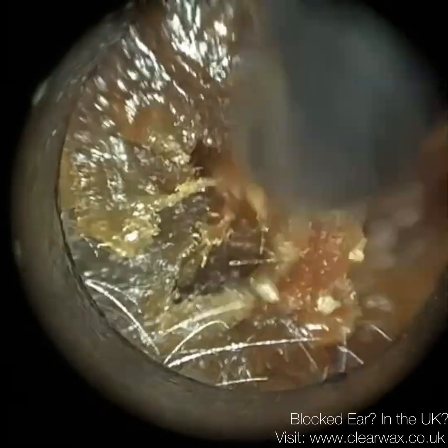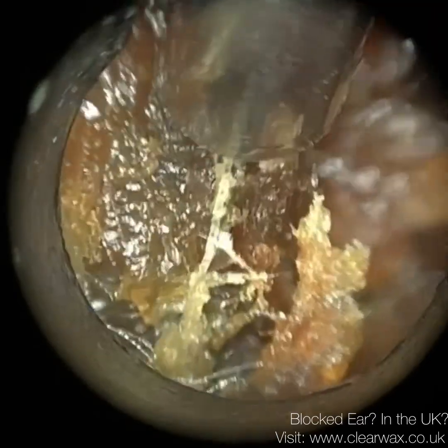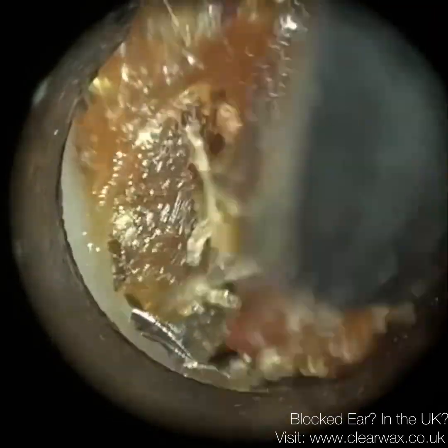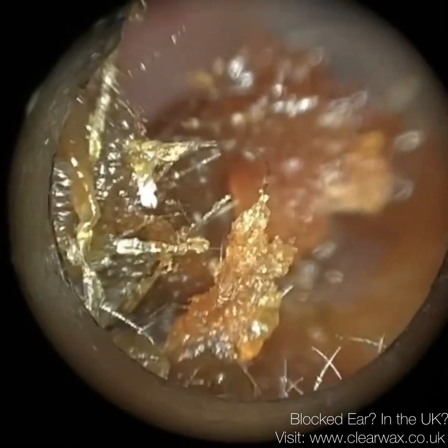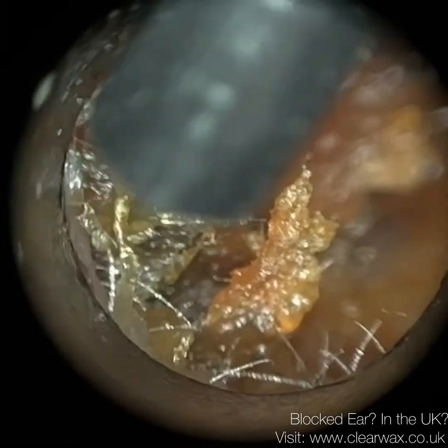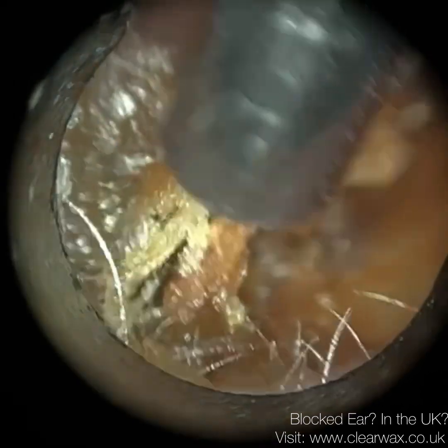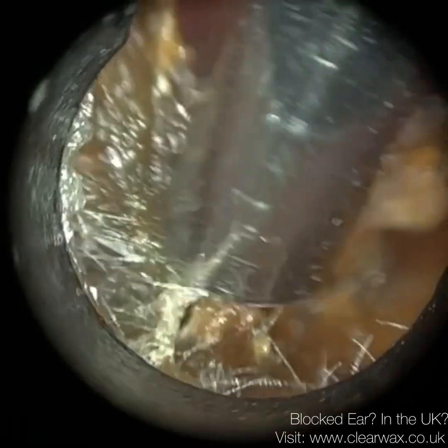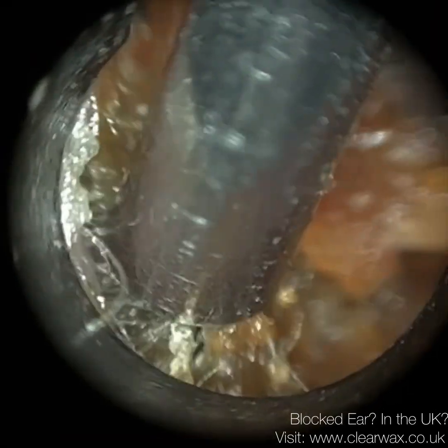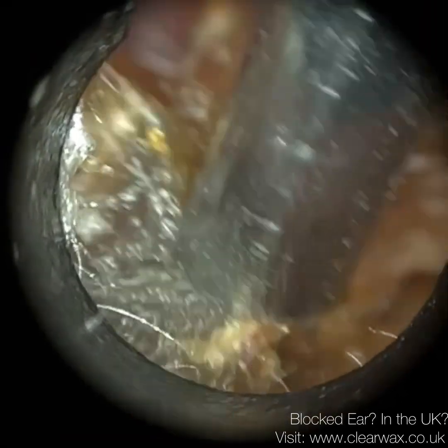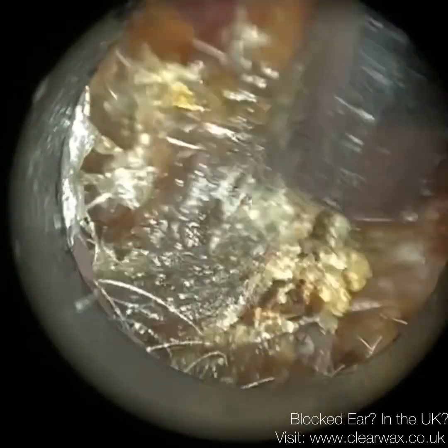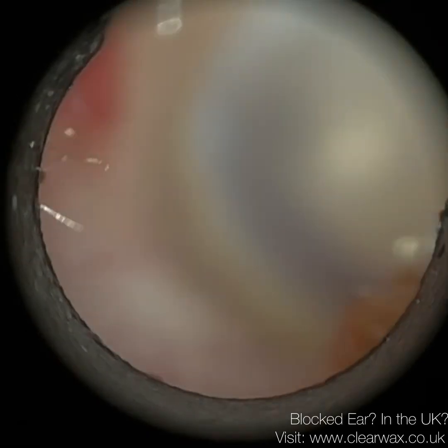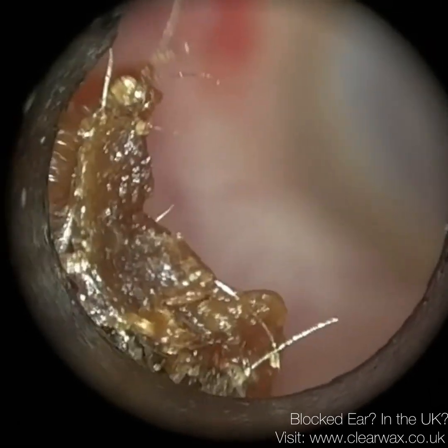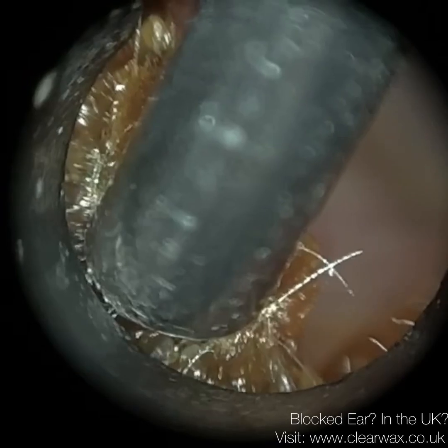It prevents wax from migrating inside the hearing aid itself, so it prevents it coming in contact with all the circuitry or the electronics. So they were having to constantly change their wax filter, because when the wax filter is blocked, it's doing its job, it's fulfilling its function, it's preventing the wax from migrating inside the hearing aid. However, amplified sound can't then be amplified into the ear because the filter is blocked. So the filter works both ways. It prevents wax from entering inside the hearing aid, but it also prevents amplified sound from exiting the hearing aid itself and into the patient's ear.